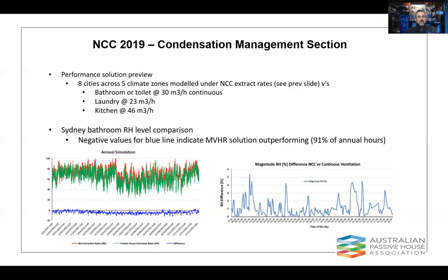But in essence, what we did was pick 8 cities across 5 climate zones, and we modelled them under both the NCC rates, those that are in the condensation section, and then also against typical passive house rates, but obviously continuous. And the NCC ones were intermittent. So we made some assumptions about how long an exhaust fan might typically run for in a bathroom. And it's typically around how long an occupant's there. No one really leaves their fan on for another few hours and comes back at morning tea to turn it off.